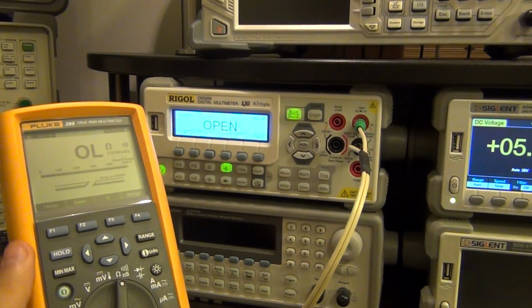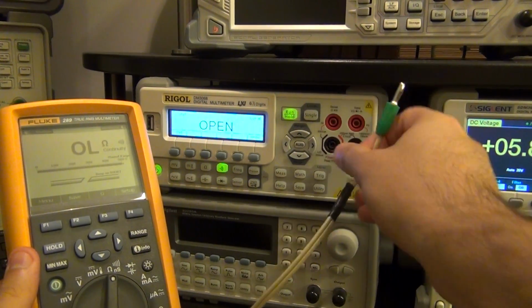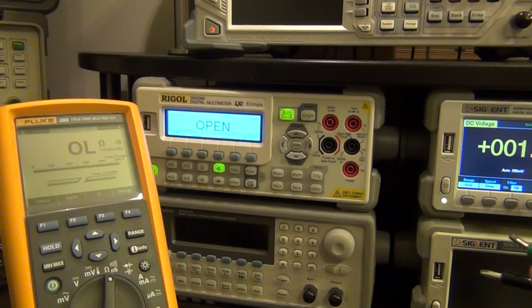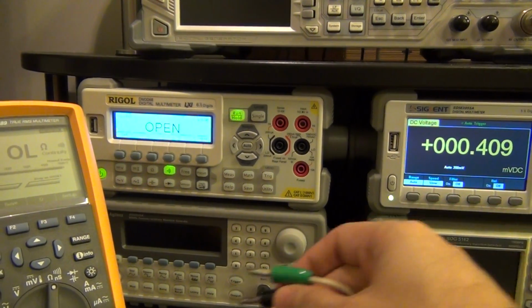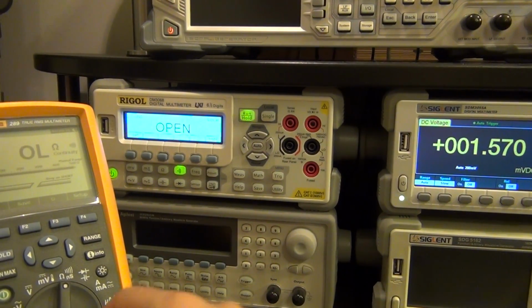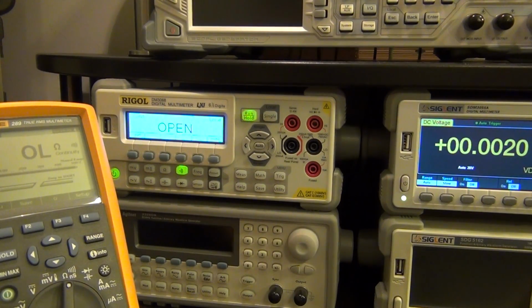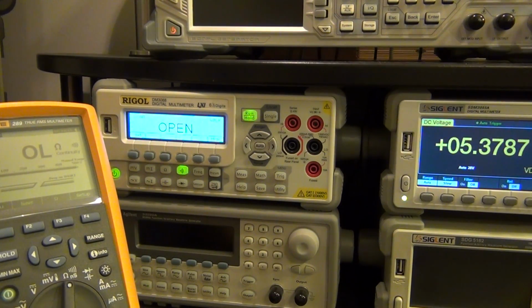So here I'm going to use the Fluke. If I plug the Fluke in, focusing on this voltage, it's also in continuity mode. I'll plug that in like so, and you can see the Fluke gives 5.3 volts, a little lower than both of the others. Something to consider—it may not necessarily be a problem, but it could cause an issue if you're measuring very sensitive electronics.